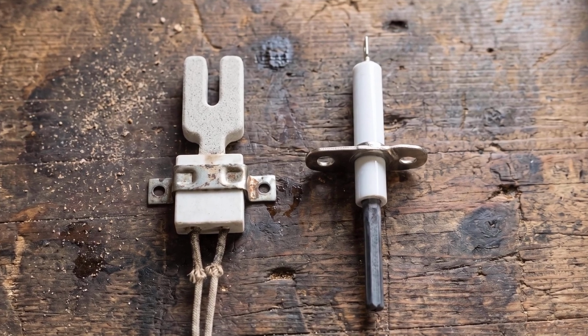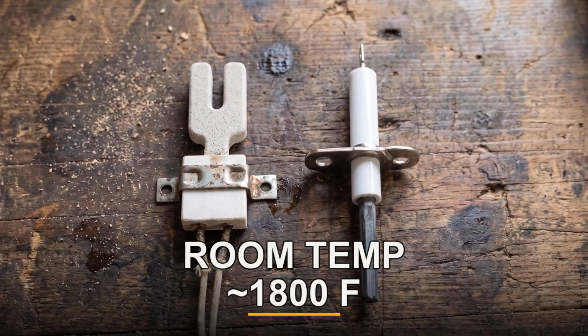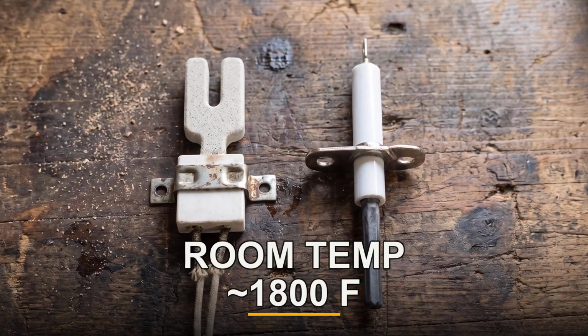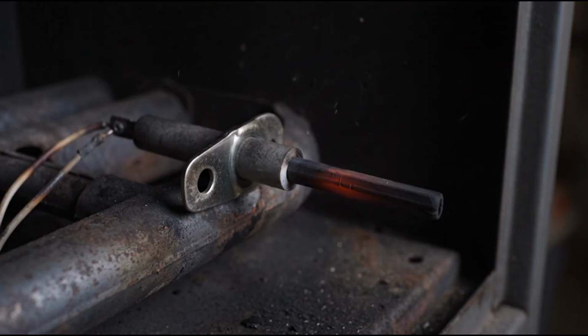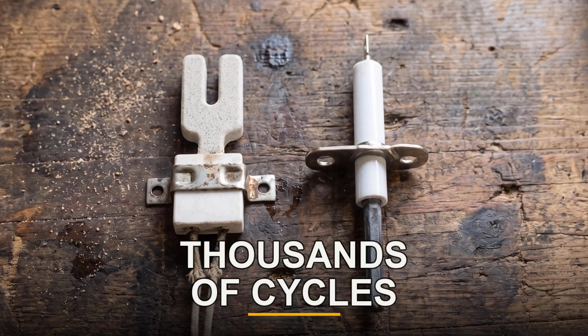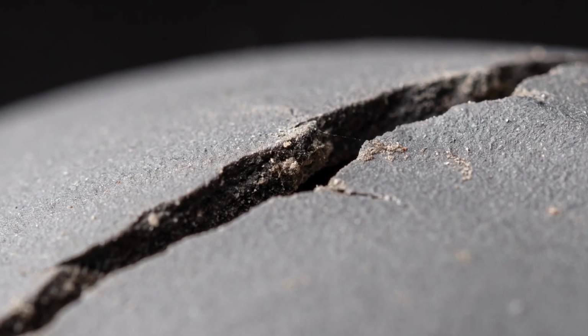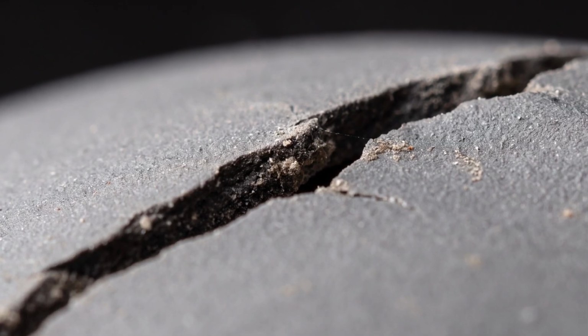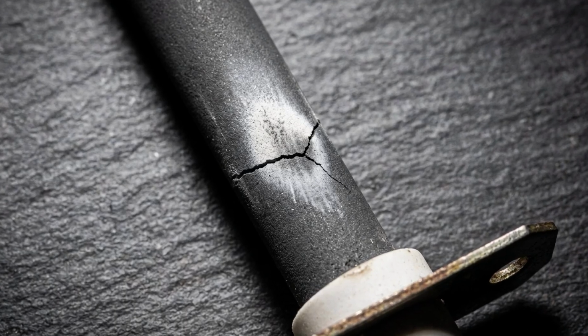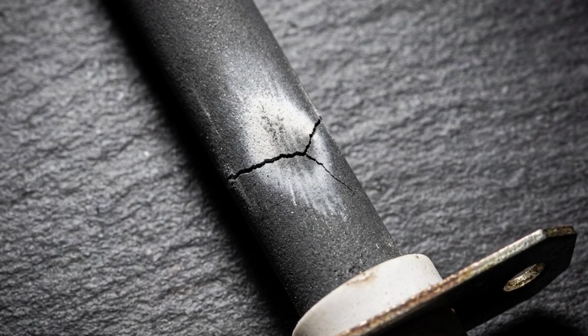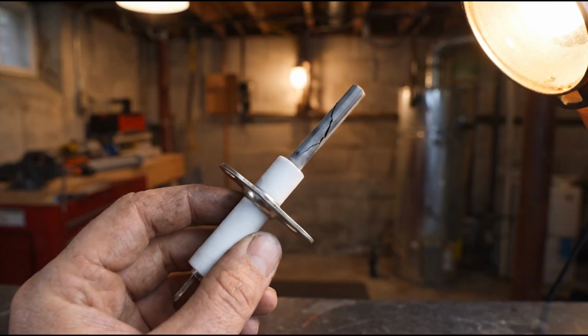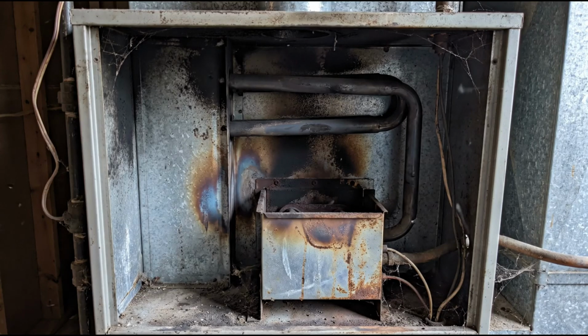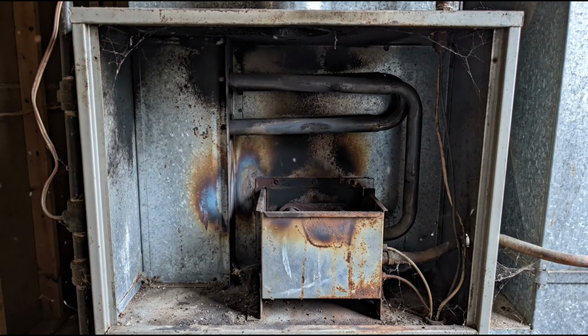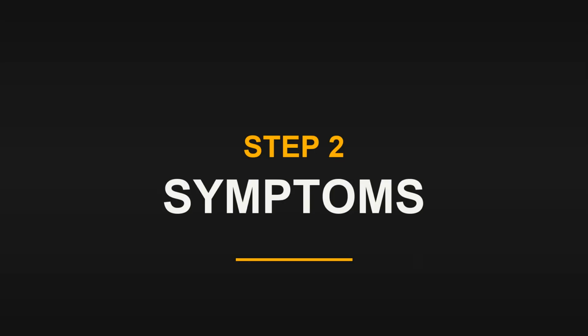Every time your furnace fires, this element heats from room temperature to 1800 degrees in seconds, then cools, then does it again. Thousands of cycles a winter. Ceramic can only take so many of those swings before a hairline crack opens, and a cracked igniter is a dead igniter. That is why it fails first. It lives the hardest life of any part in the cabinet. Step 2. The symptoms.